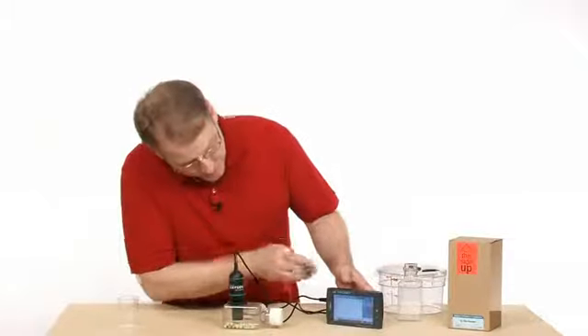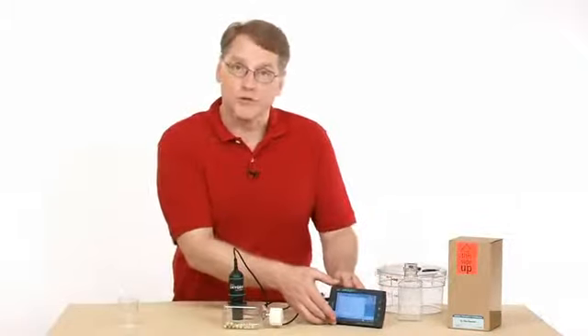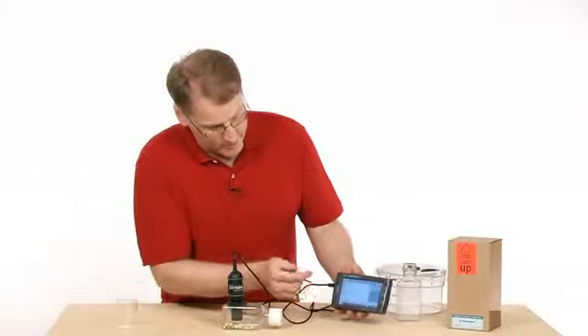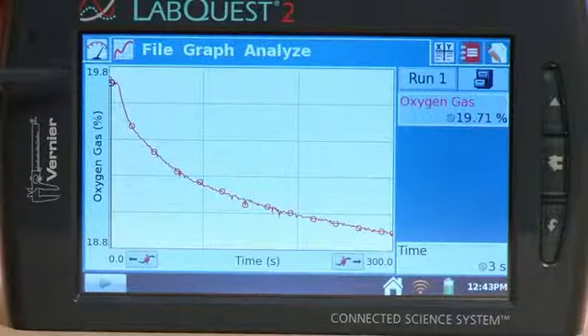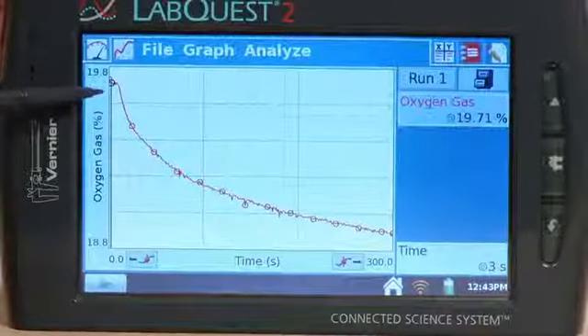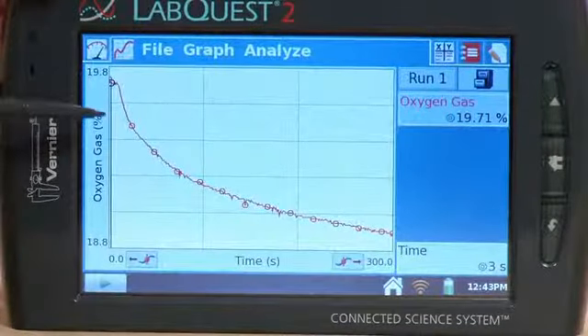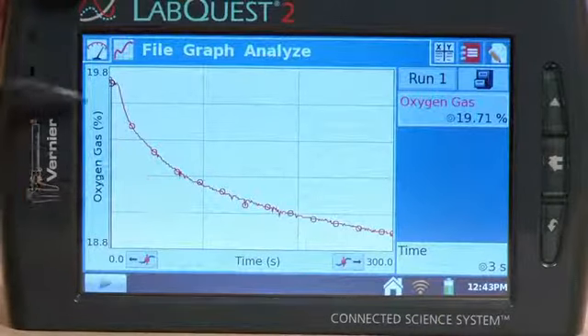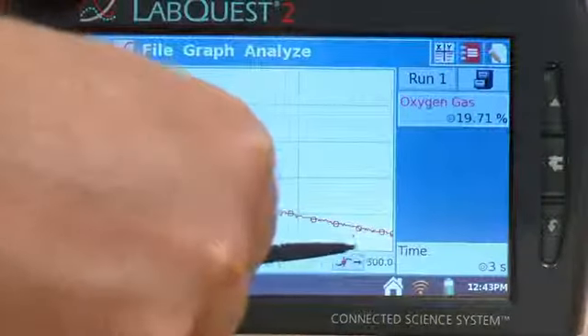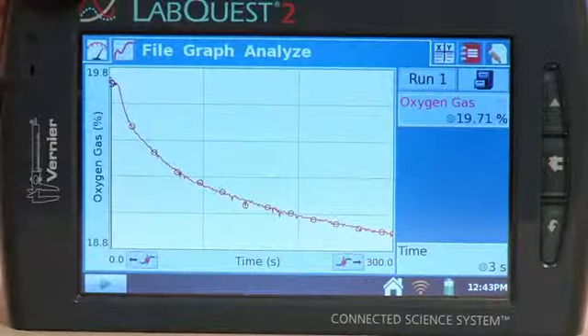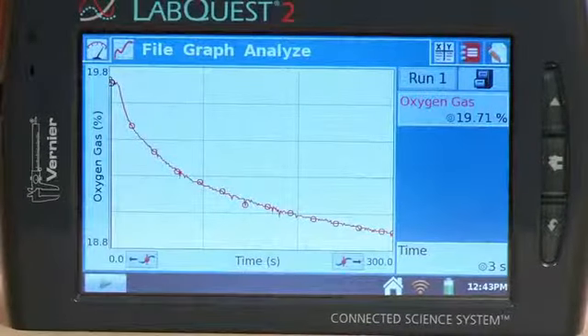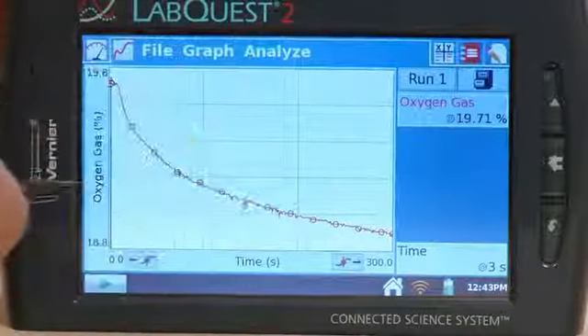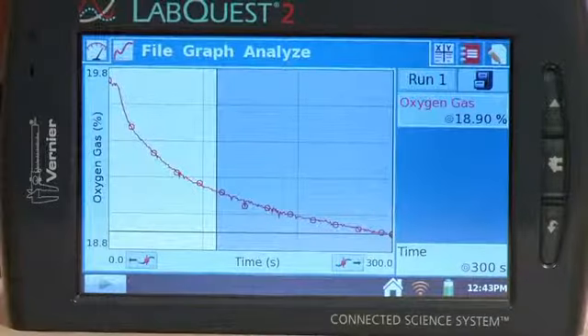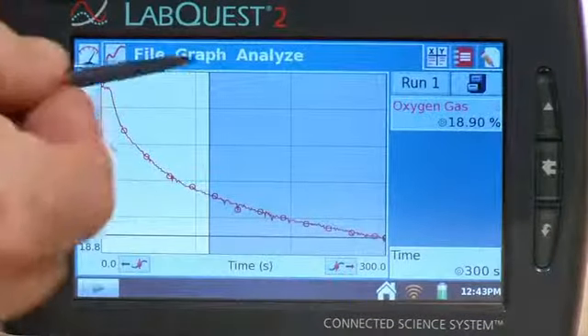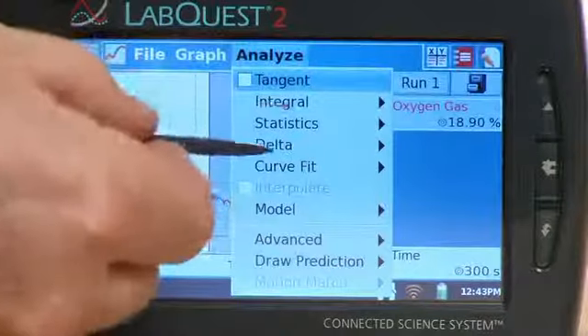Our data is complete, and so we might want to be able to do some analysis here. If I look at my data, we see that this first part, it dropped fairly rapidly because I just put the sensor into the bottle and the peas had actually already been in there just a little bit. And so we saw this drop there. But this last part there looks like it kind of levels off and becomes a fairly linear portion. And what I would like to do is analyze this section of the data. And so I'm going to highlight that. And so I'm highlighting just that region of the graph. And that way when I do the curve fit, it will use just those data to calculate that.